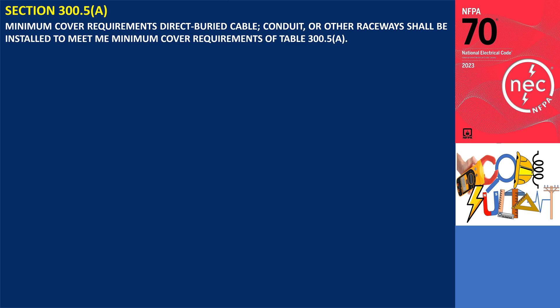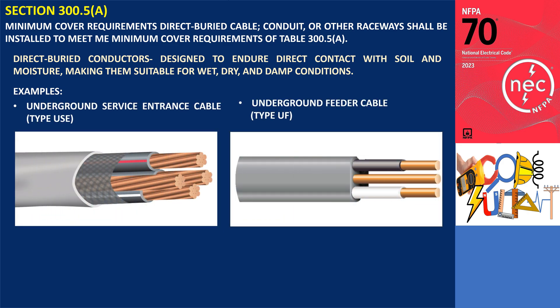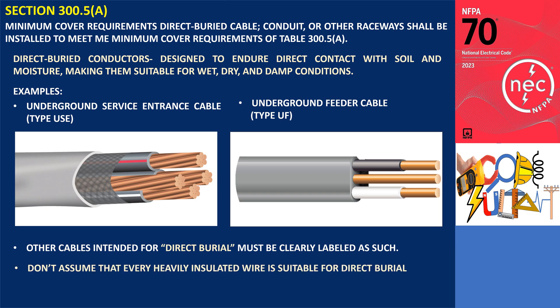Section 300.5(a) outlines the minimum cover requirements, stating that direct buried cables, conduits, or other raceways must adhere to the minimum cover depths specified in Table 300.5(a). Direct buried conductors are designed to endure direct contact with soil and moisture, making them suitable for wet, dry, and damp conditions. Examples of direct buried cables recognized by the code include Underground Service Entrance cable, type USE, and Underground Feeder cable, type UF. Cables intended for direct burial must be clearly labeled as such — it's important not to assume that every heavily insulated wire is suitable for direct burial.